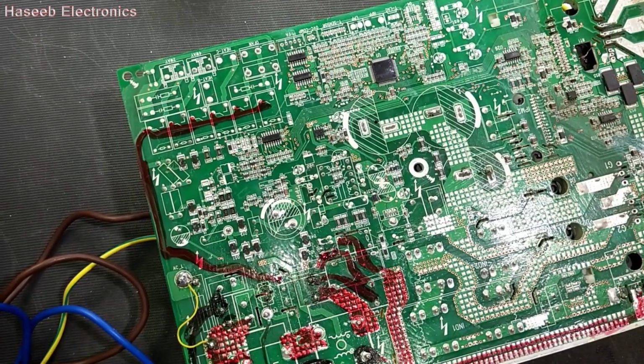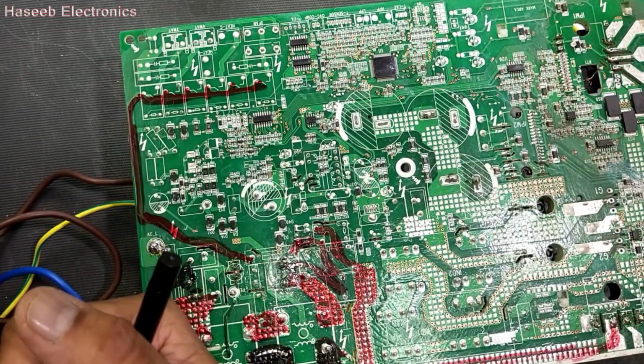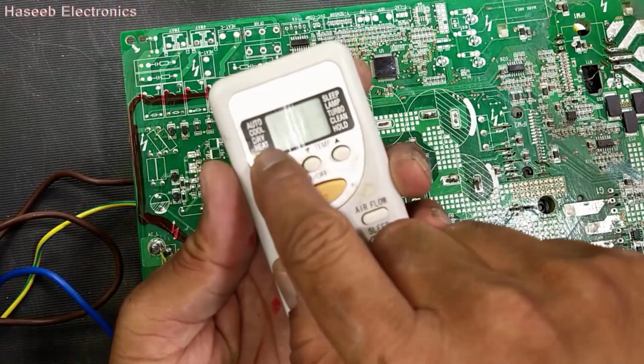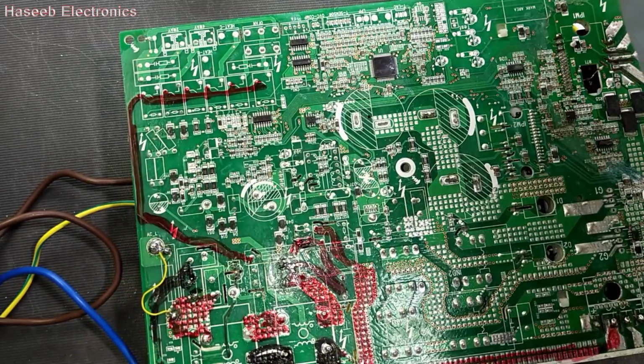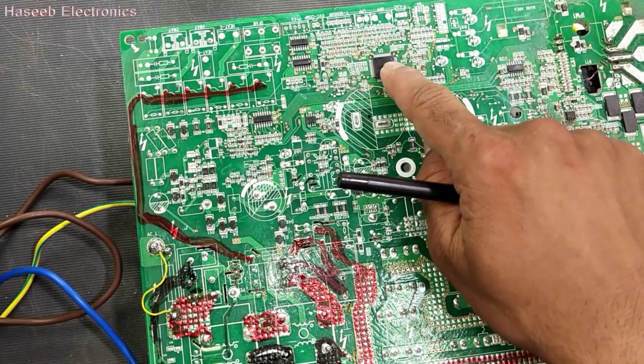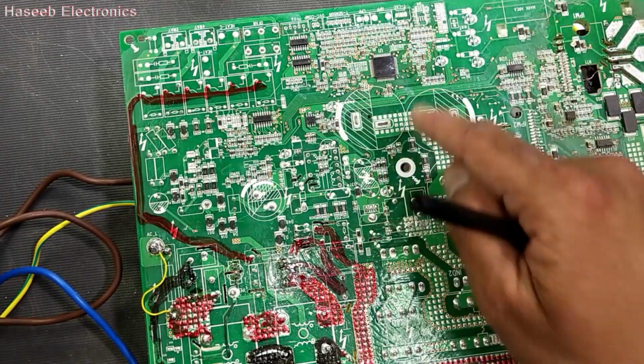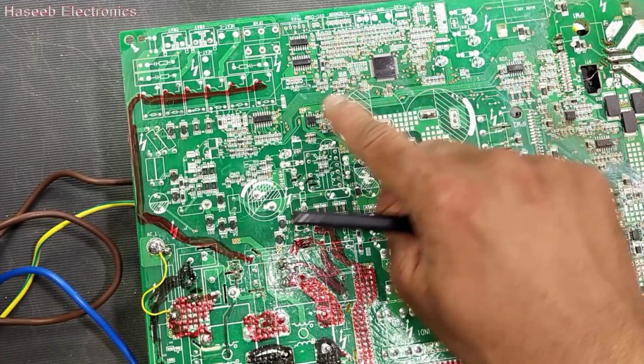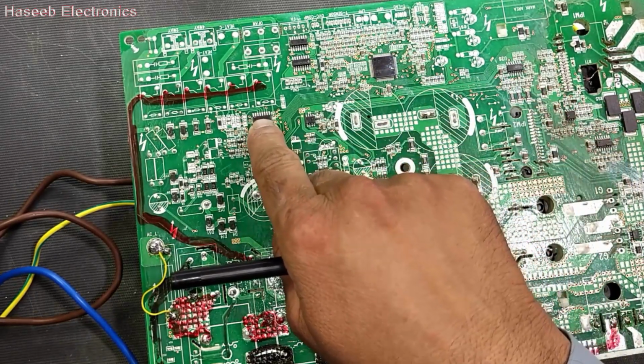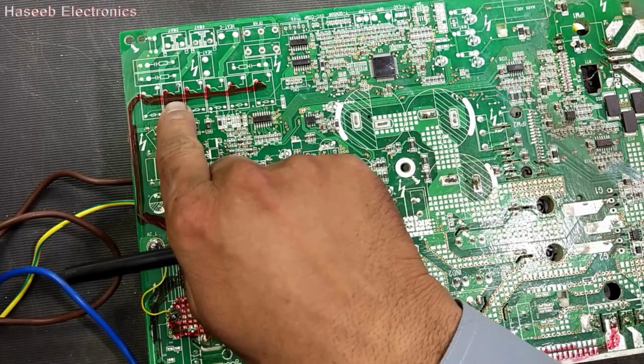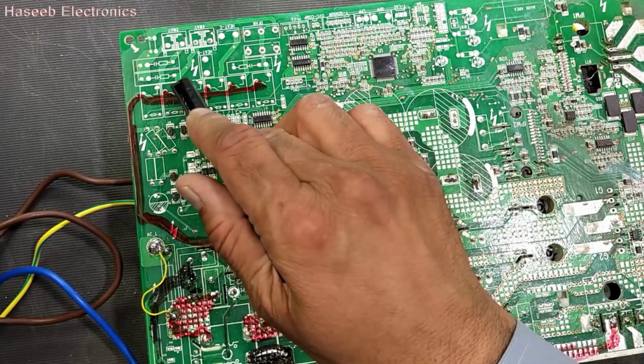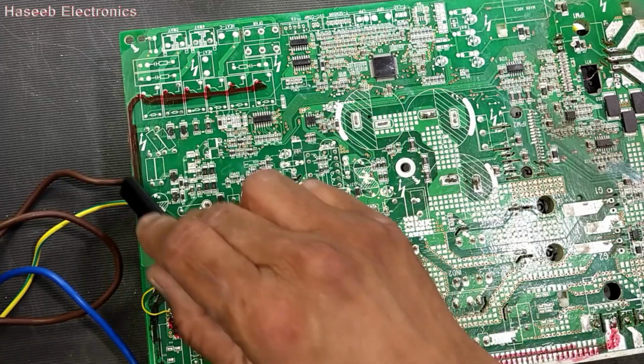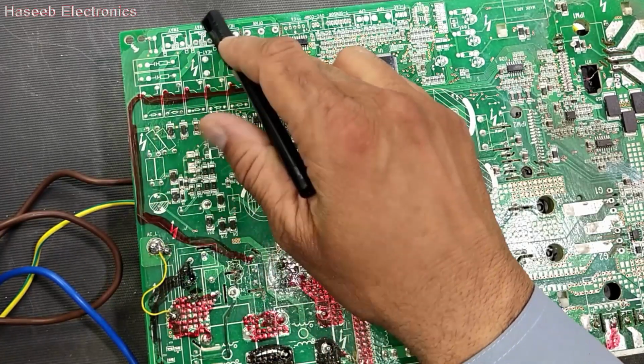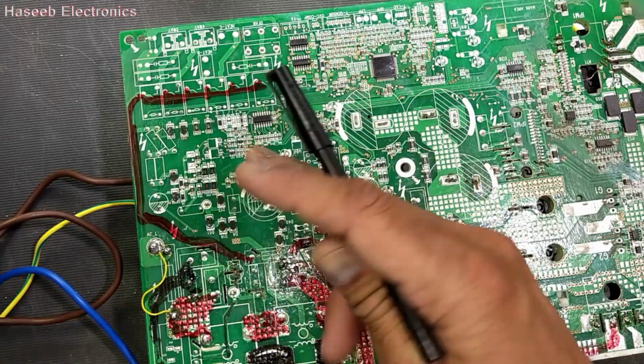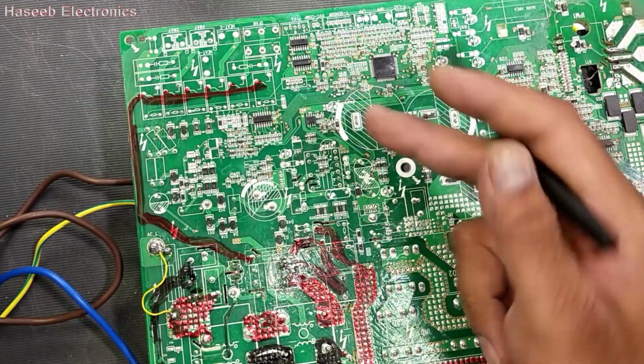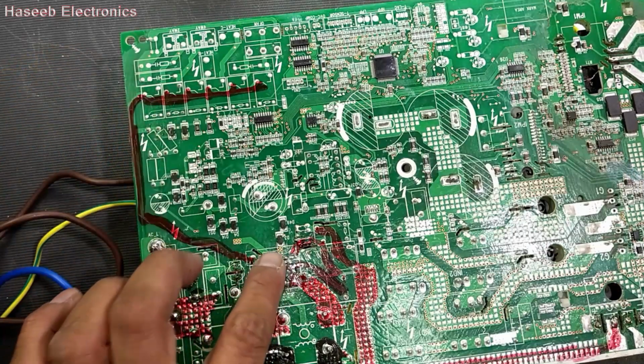When we press the heat mode switch on our remote, we shift the system to heat mode. A command from the processor is generated from the indoor unit to this processor, and this processor generates a signal to this ULN2003 IC, which drives the coil. At that time line voltage is switched through this relay and goes to the four-way valve to swap the valve into heat mode. So this is the line voltage function from this fuse.